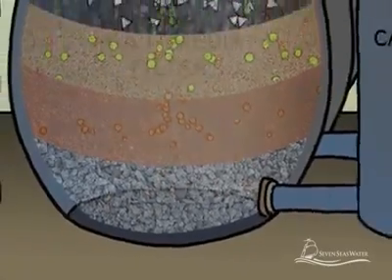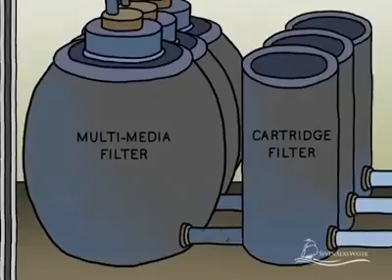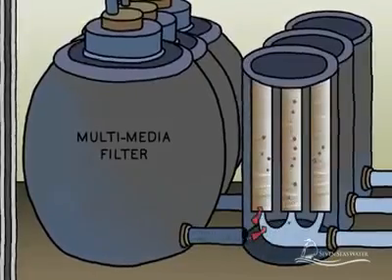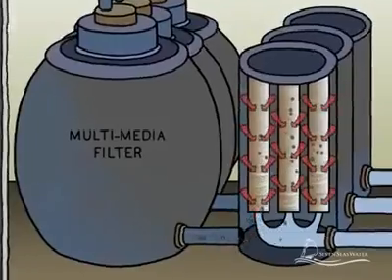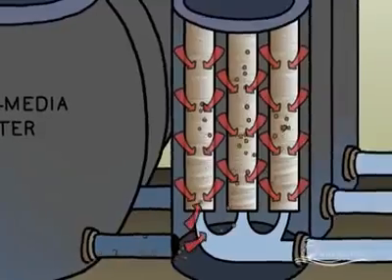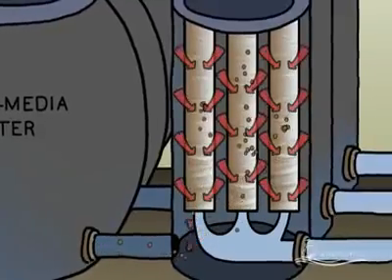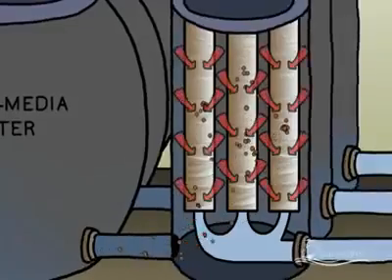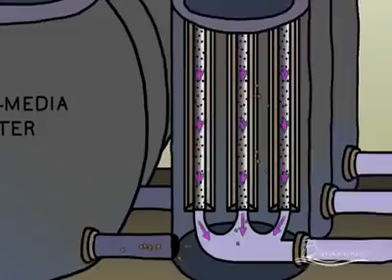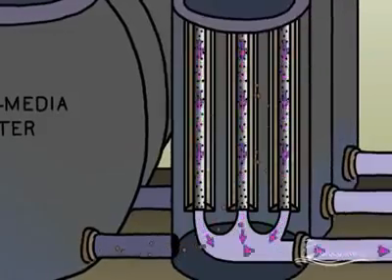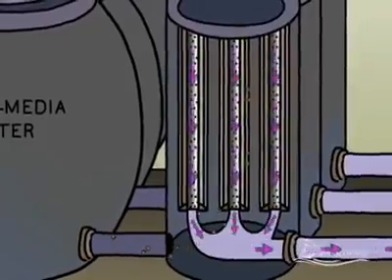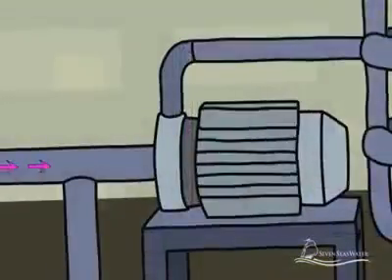Next, the filtered seawater travels to the cartridge filters, which act as a second stage of filtration. Cartridge filters used for seawater reverse osmosis are typically made from a yarn-like synthetic material that is wound into cartridges. These remove even smaller solid particles from the seawater, such as fine sand and clay, before the seawater proceeds to the reverse osmosis membranes.